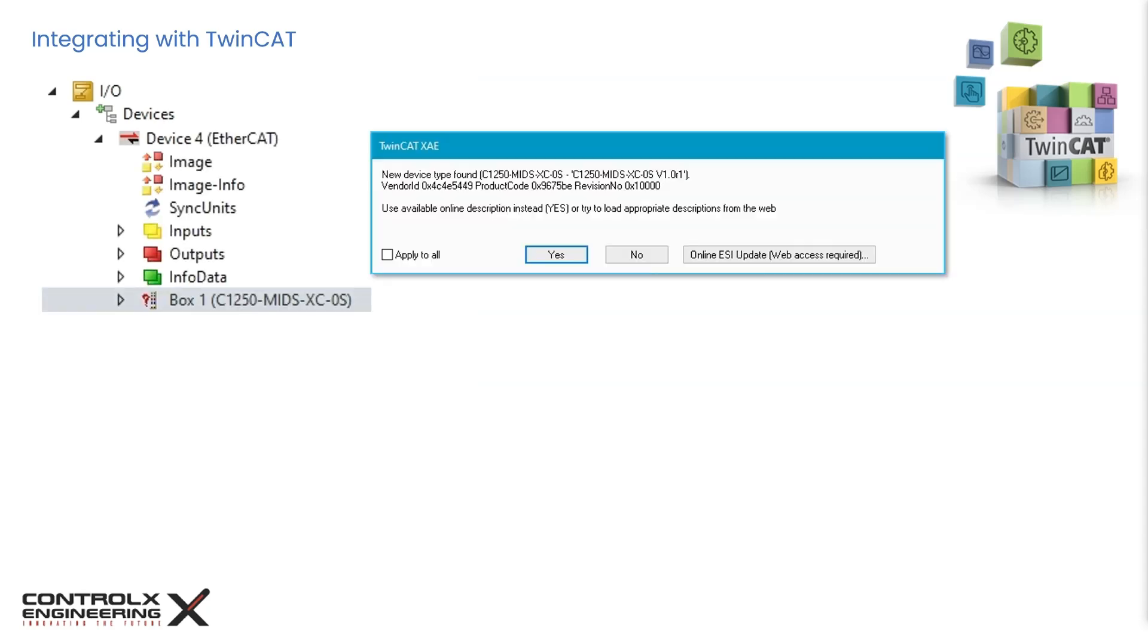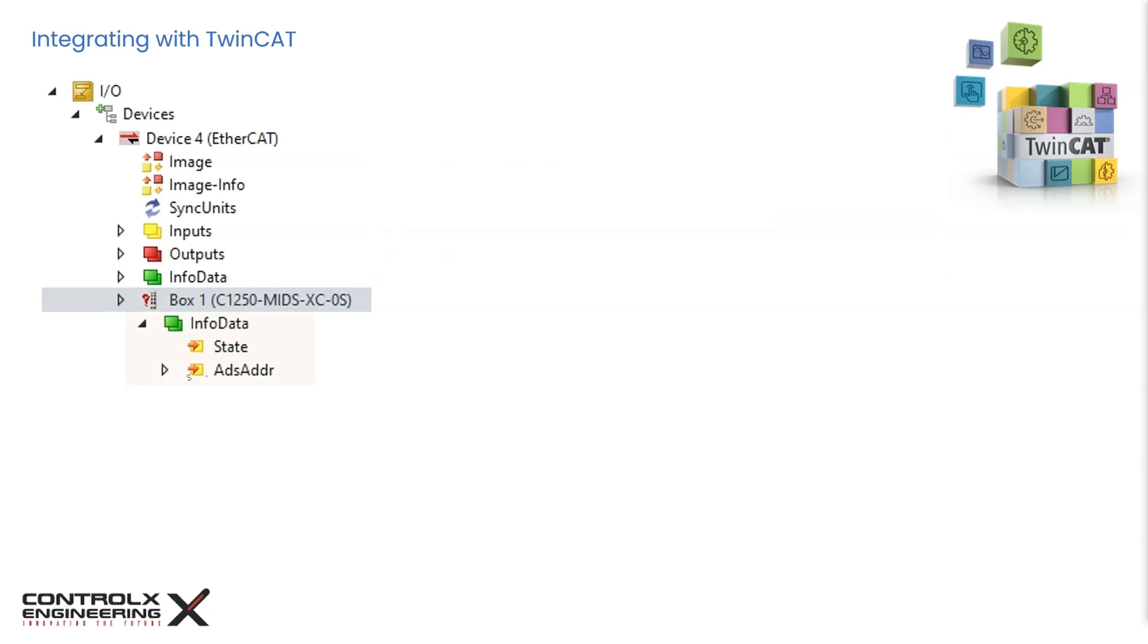If the ESI file is not available, then TwinCAT will prompt you with a message box stating that a new device type was found. As you can see, I performed an online scan and it detected the LinMot servo, but because of the missing ESI file, no useful objects are available and this configuration is not usable. To correctly set up the slave device, the corresponding ESI file must be made available and the configuration process should be repeated.